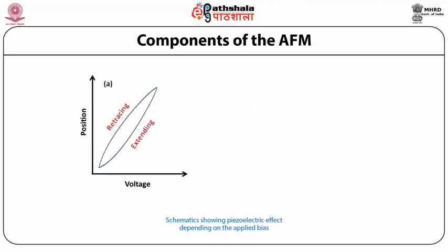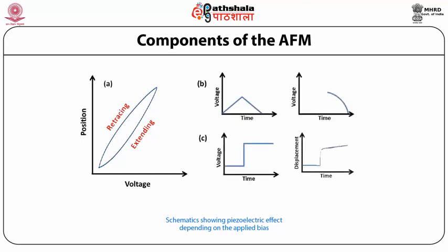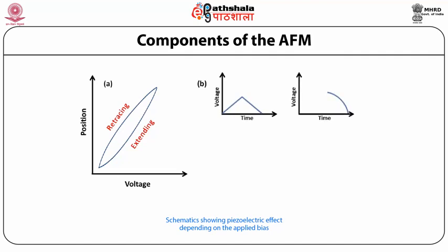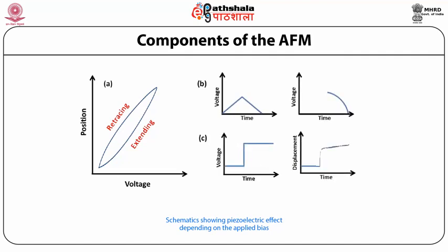Creep. The drift of the piezo displacement after a DC offset voltage is applied to the piezo ceramic is known as creep, and occurs either by changes in X and Y offsets or while using frame up and frame down, such that the piezo rapidly travels over a large area to restart the scan.